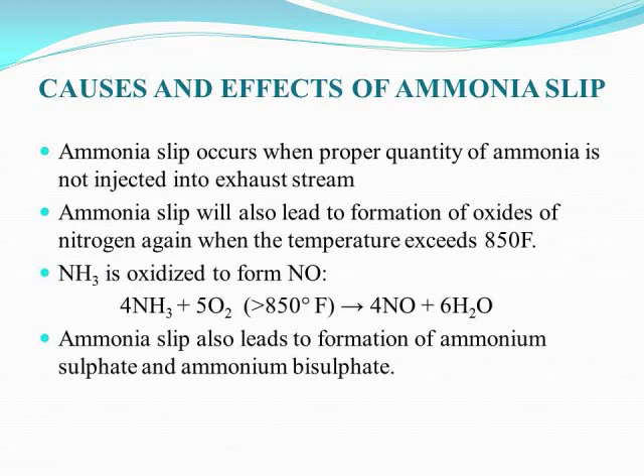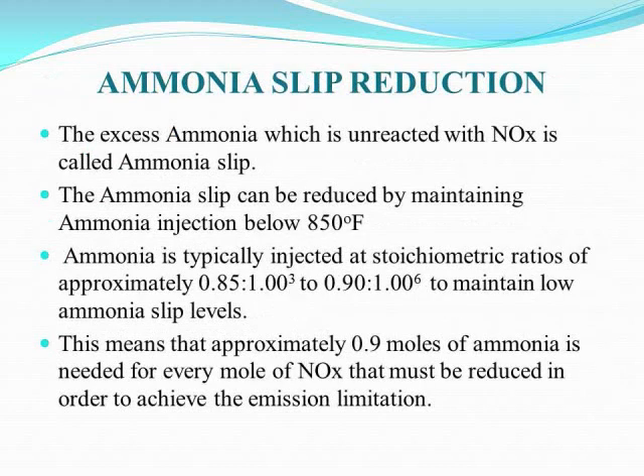Let us see what ammonia slip means. Ammonia slip will occur in this SCR system but can be rectified. The effluent gas stream leaving the SCR system contains unreacted NOx and small quantities of ammonia. Ammonia emissions are generally termed ammonia slip — it is the reagent that has passed through the SCR catalyst without participating in the chemical reaction.